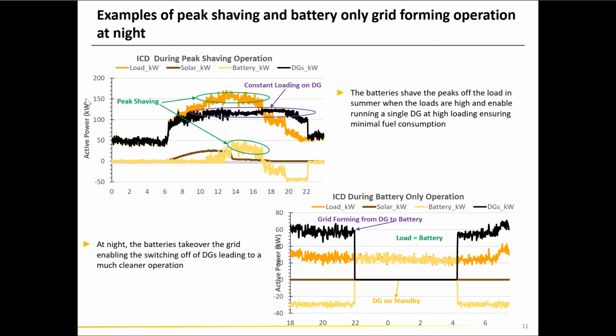I hope at some point in the future we'll get to that stage at the grid level, but this is a very unique application where you can see peak shaving and also run the grid on batteries. For this, you need a PCS that's able to form a grid with specific capabilities, and some challenges you'll face are in transitioning between different sources of generation, where the controller plays a very critical role, because it looks at all sources of generation and ensures a smooth transition.